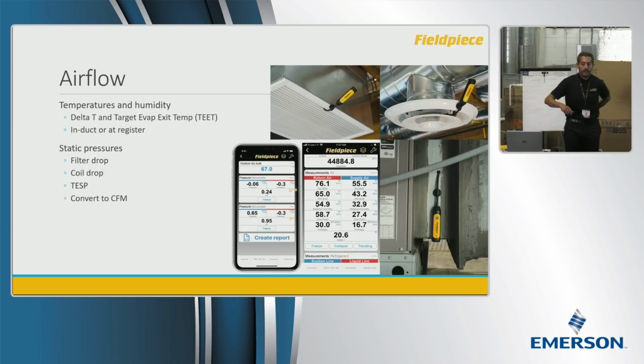So back to our role play scenario: the air wasn't coming out as cold as it should. We confirmed it quickly with a delta T test and with a target evaporator exit temperature, and we found a good amount of restriction on the return side. So we replaced the filter and did some work to help improve things on the return side. Now, since our probes are already hooked up and transferring the measurements, we see that we've improved it, but we haven't fixed the problem yet. The air's still not coming out as cold as it should be. So in this case, we're probably going to have to start measuring some pressures and temperatures at the outdoor unit. Let's move on to that.